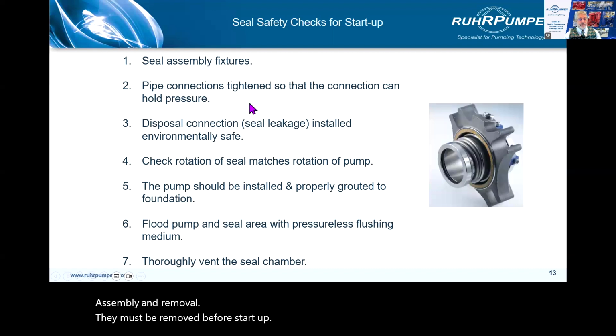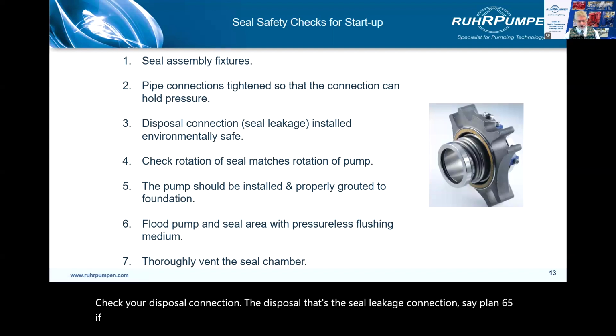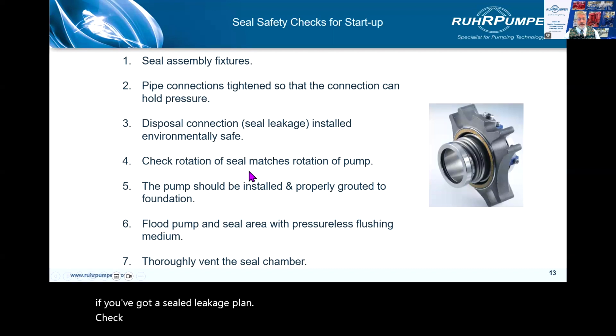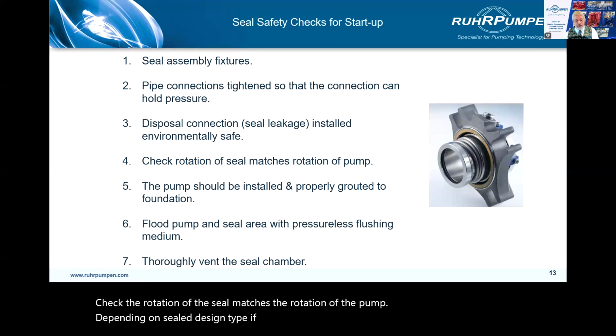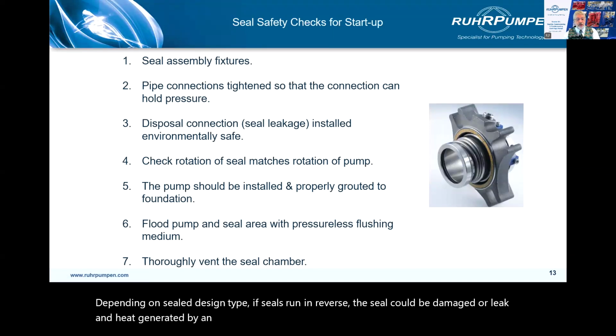Check the pipe connections: seal flush, quench, leakage plan. Check your disposal connection. The disposal, that's the seal leakage connection, say a Plan 65 if you've got a seal leakage plan. Check the rotation of the seal matches the rotation of the pump. Depending on seal design type, if seals run in reverse, the seal could be damaged or leak. And heat generated by an improperly installed seal could incur further damage to the pump.